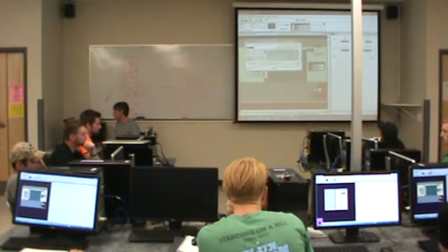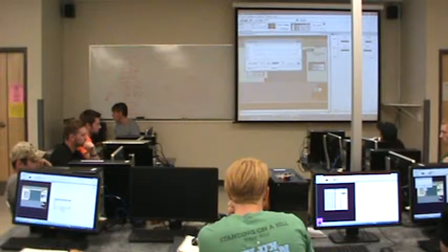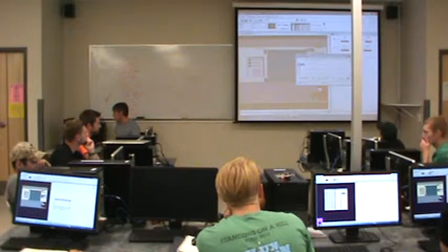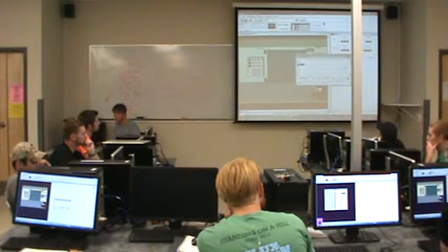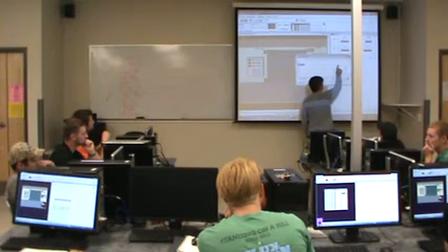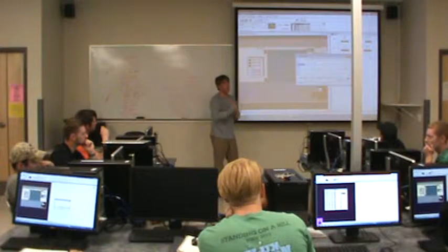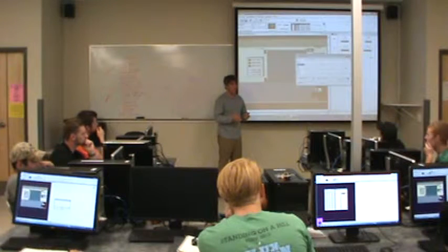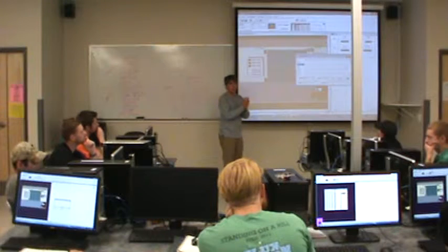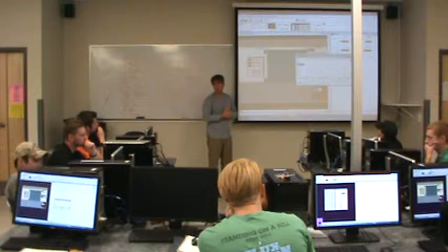So grab the data table, which is the hammer and the wrench, and I'll choose the input file, and I will look at bit 3 and bit 4 on word 1. Here's word 1. It's this whole line, all 16 of these bits right here are word 1. I'm interested in bit 3 and bit 4. I look at them, they are on. What that means is that this is a normally open switch. Okay? So, right now, this switch is passing power because it's been closed. But its natural state, without the door in the way, is to be open, the spring is open.